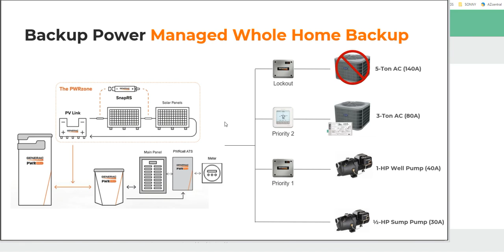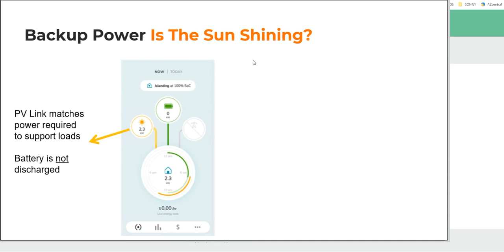All right, and lastly, backup power. This is an important distinction when talking about DC coupled systems. If you are looking at an AC coupled system, then in many cases during an outage you're always powering the home from the battery. Sometimes the solar array is on, sometimes it's off, depending on the state of charge of the battery and how much sun is shining, and whether or not the battery system can handle the full capacity of the inverter.